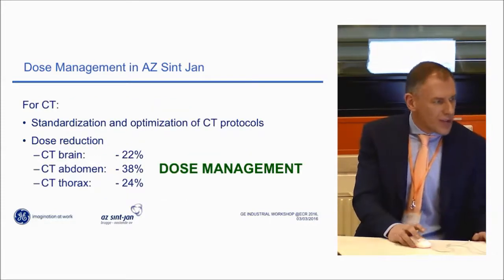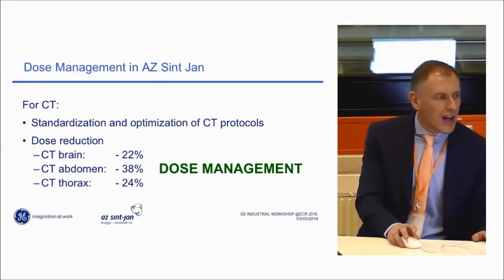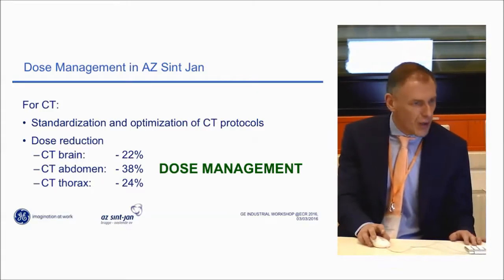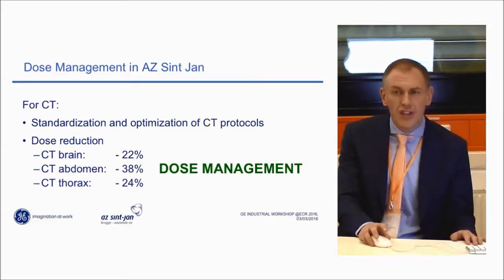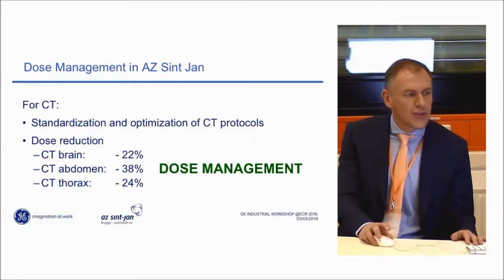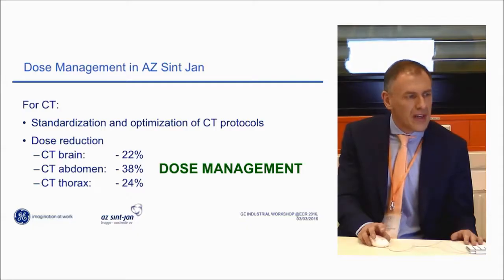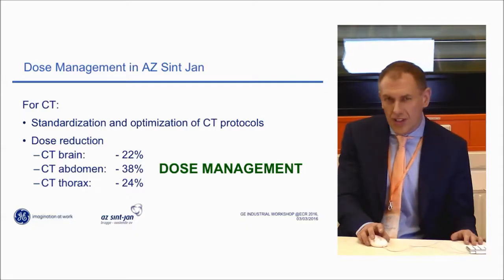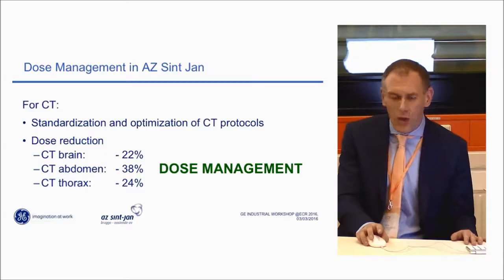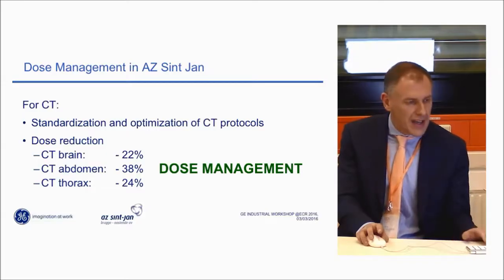For CT especially, we worked a lot on standardization and optimization of all our CT protocols, and we could achieve some reasonable dose reductions — up to 38% for venous CT of the abdomen. Using the DoseWatch system, this led to better dose management, at least at our department.